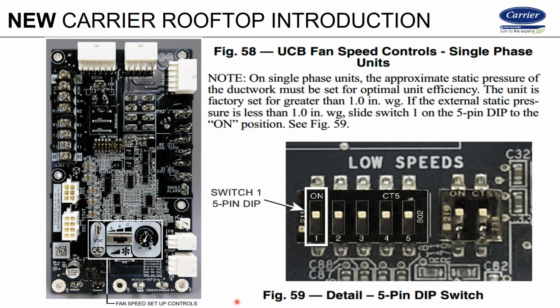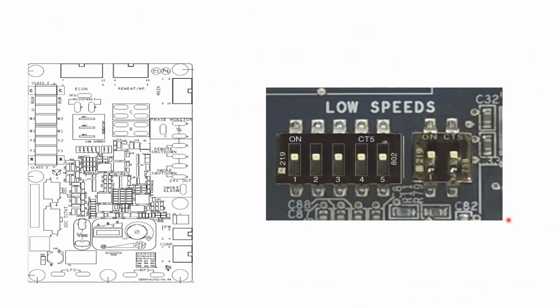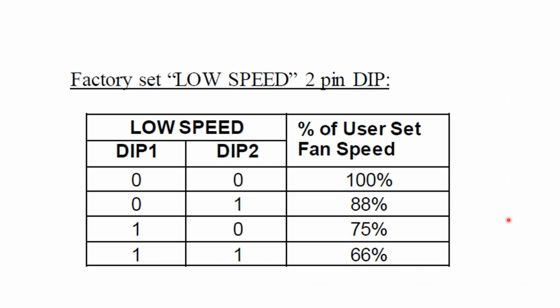If you ever run into a board that fails, these are all going to come out defaulted at the off position. So make sure that you look at the board you're changing out, look at the current dip switch settings, and then reset these on the new replacement board before starting the unit, because this is going to set the tonnage that this board is in. It's going to set the drive package and motor combination as well. So just better look at the dip switches.